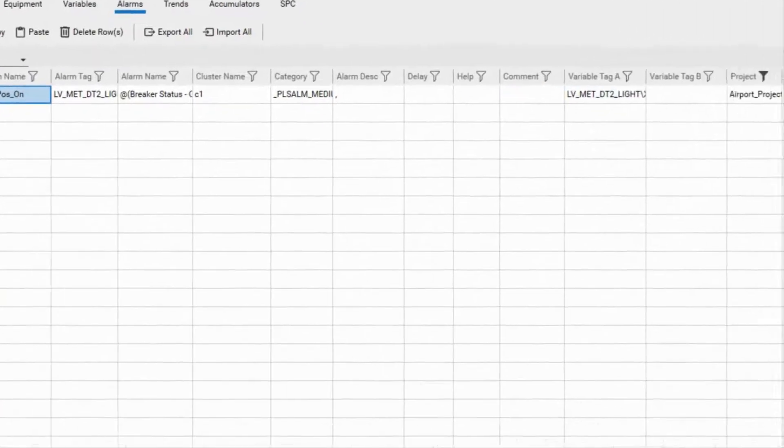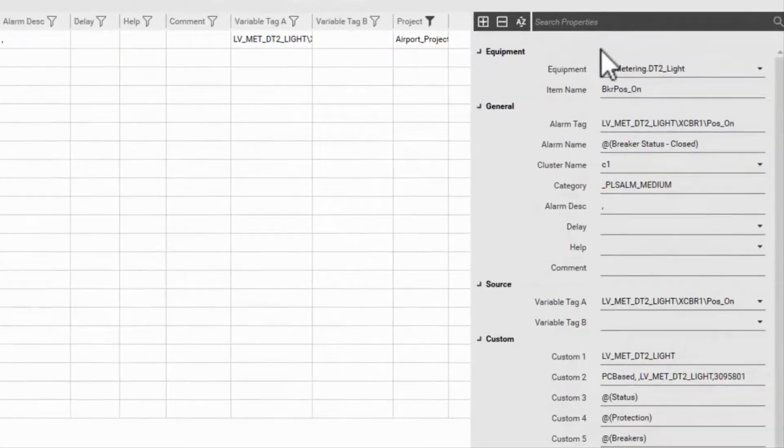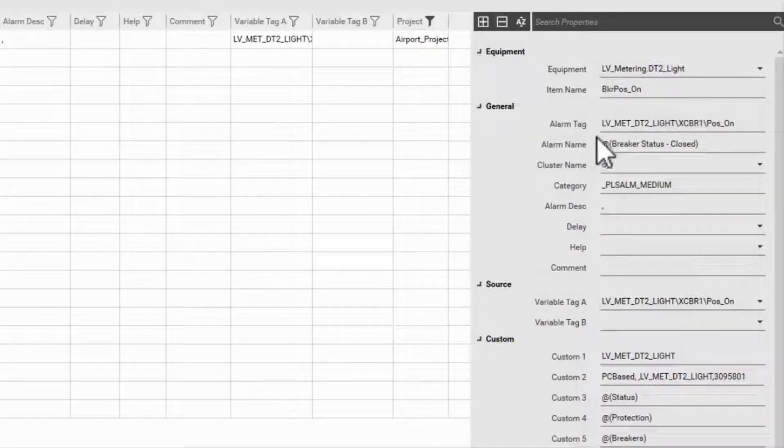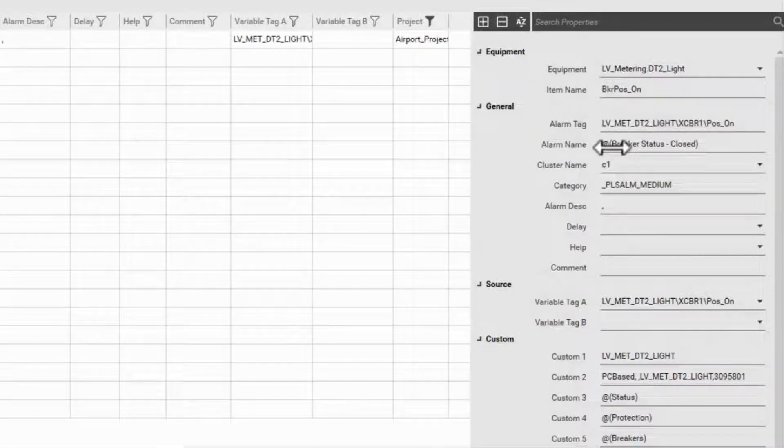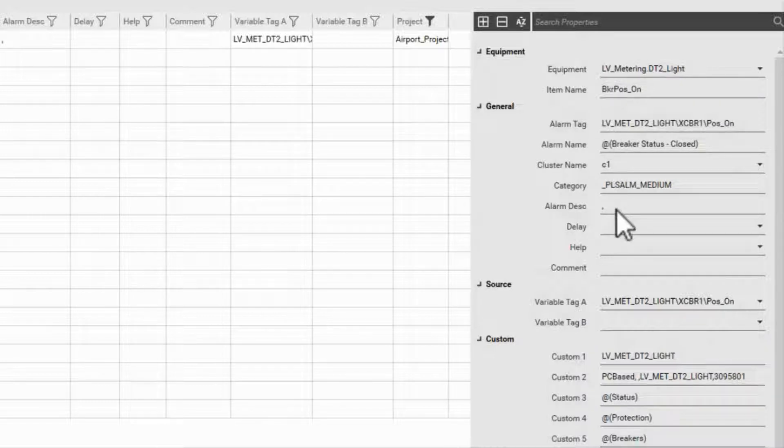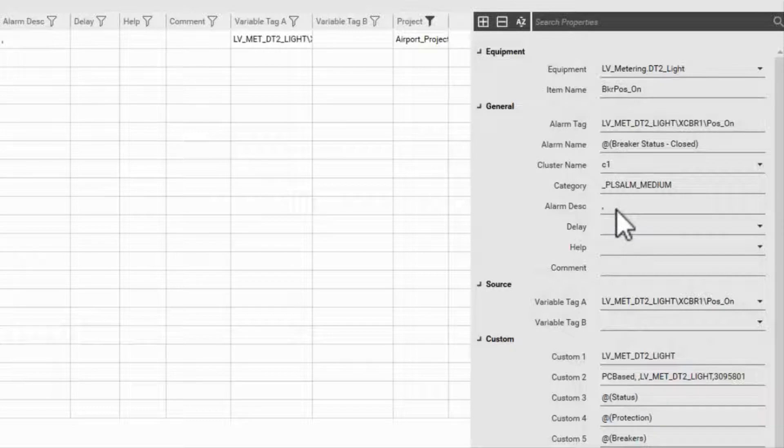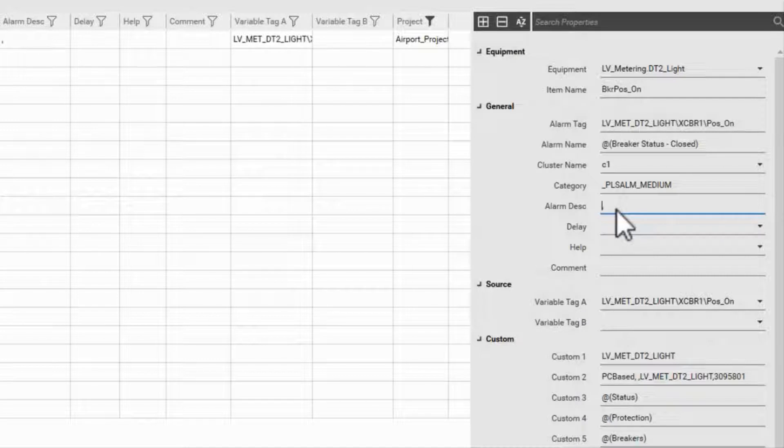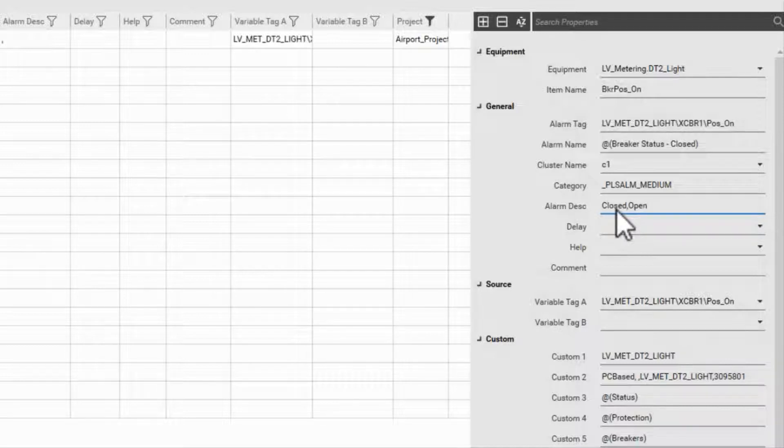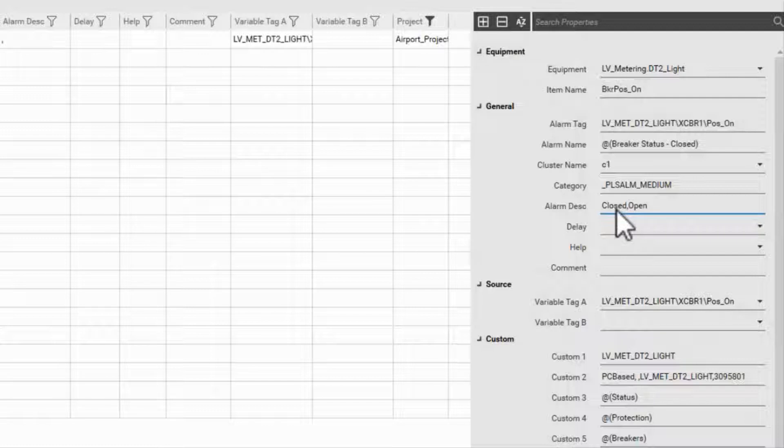If I go down the fields here, many of these will be familiar from looking at the variable tags. Note that the alarm name is the description that shows up in the alarm views, while alarm description is the text used for each state. This is in order of alarm on text comma alarm off text. This was filled out as part of the variable tag and we'll use the system defaults if left empty.